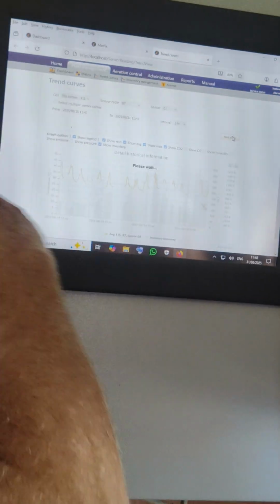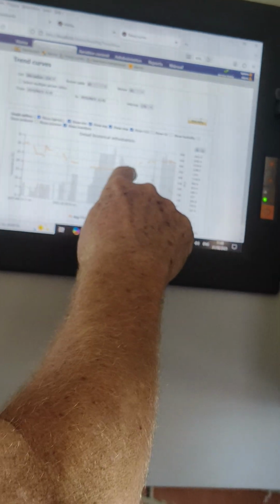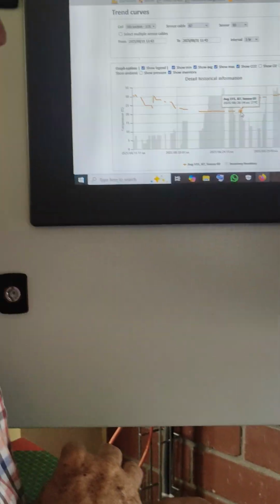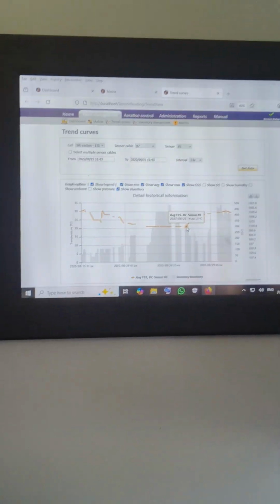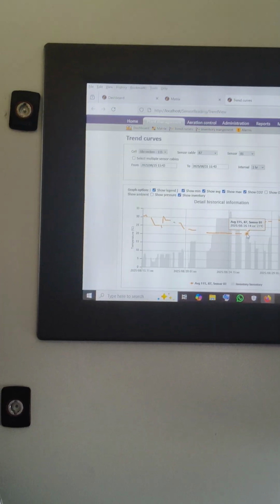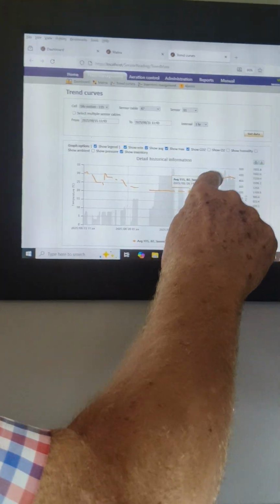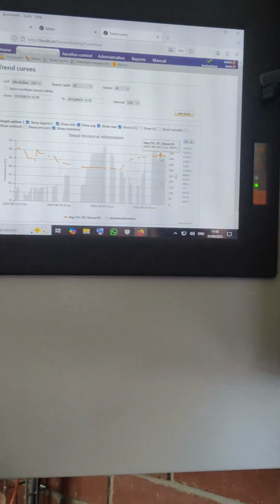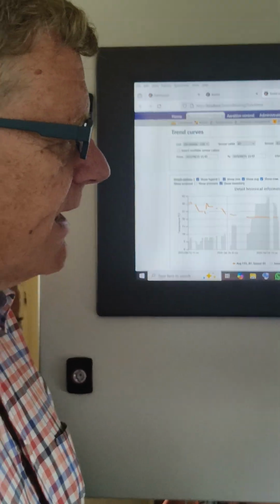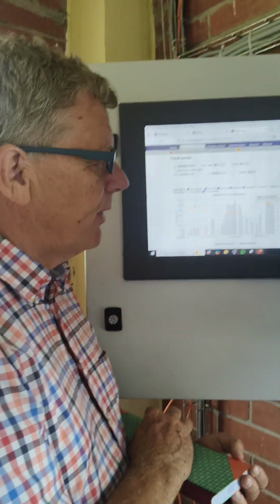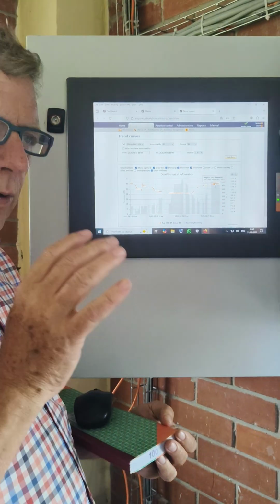And if we go down to sensor 1, which is the lowest, then we will see a flat curve for some time. So here you had some grain. But I can guarantee you that on the 26th of August, you did movements in that silo. I can see that. And that is why the temperature changed. Why did the temperature change? Well, maybe because the grain coming from higher up was warmer. It looks like that. And right now, at the lowest sensor, you have grain that is 30 degrees, relatively stable there. So right now, it looks like you're not unloading anything.